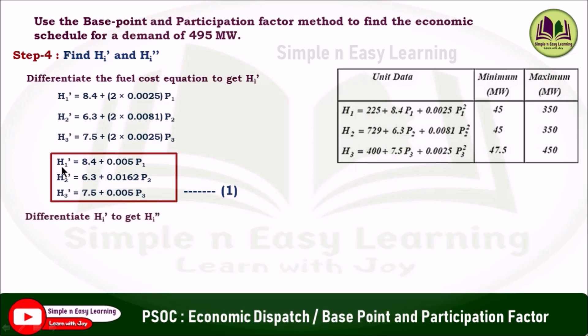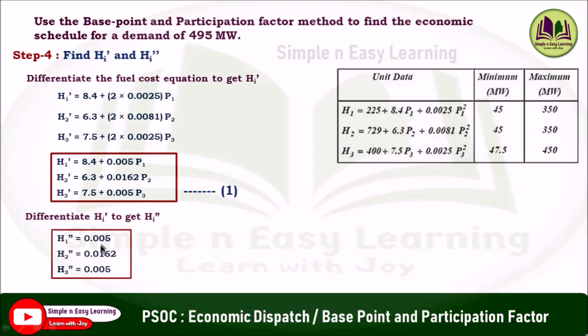Now differentiate h_i' to get h_i''. Differentiating h1' = 8.4 + 0.005·P1: the constant 8.4 gives 0 and 0.005·P1 gives 0.005. So h1'' = 0.005. Similarly, h2'' = 0.0162 and h3'' = 0.005. Take these as the second set of equations.